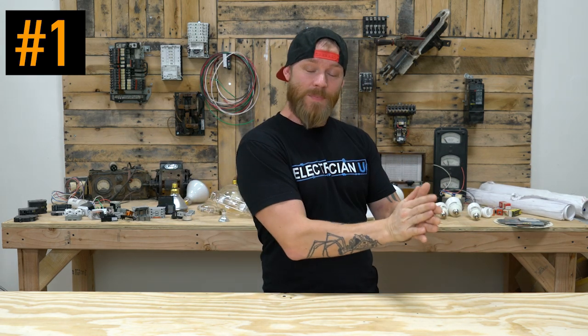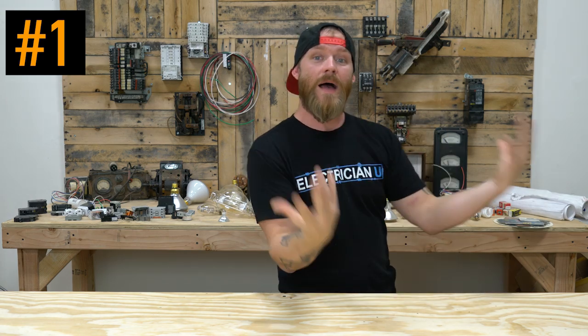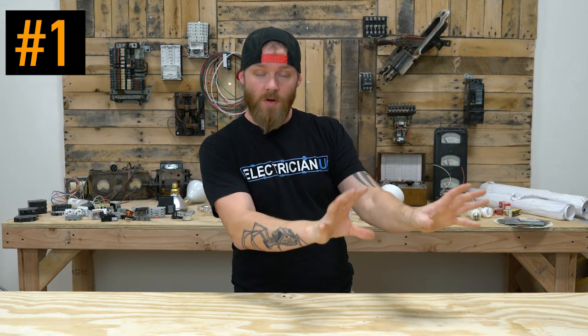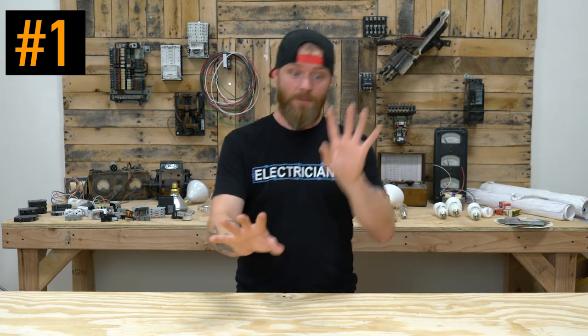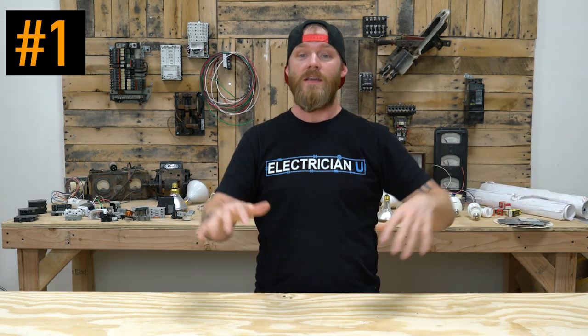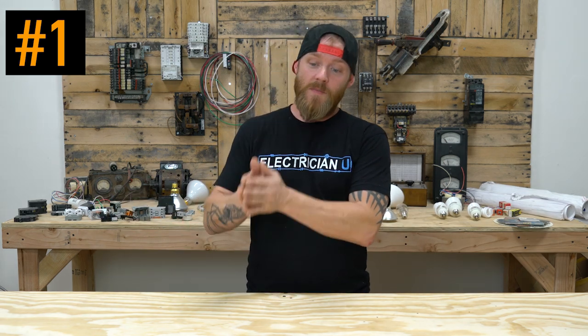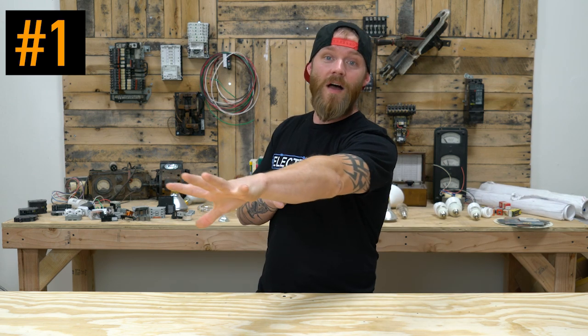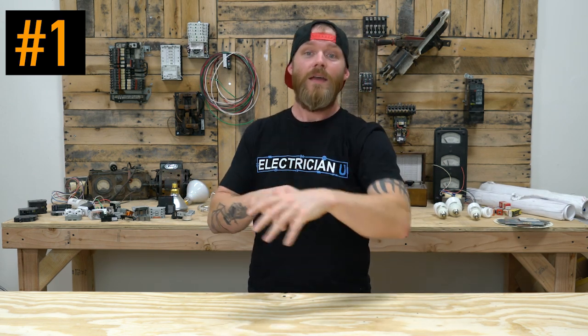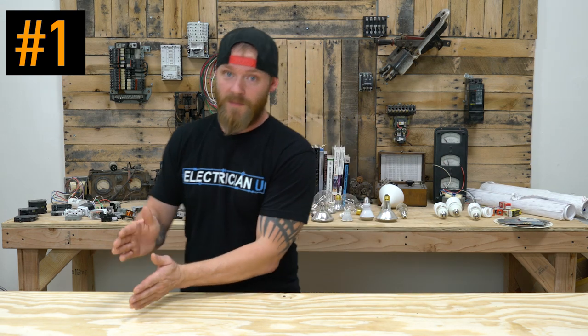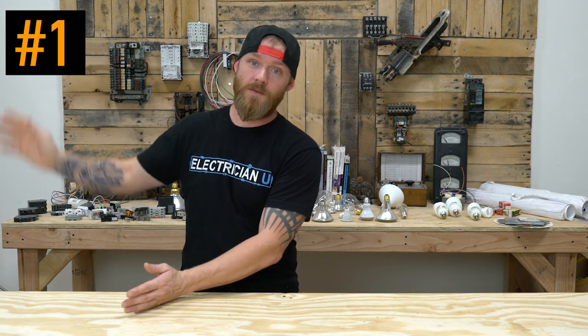So you have your service, then you've got all of your panels, you've got all this other equipment, and then at the very last panel, you've got all of these circuits that come out of it and go to devices. Those are all branch circuits. You could also have several panels that have their own branch circuits, but it's basically from the point of the last circuit breaker out to a device somewhere or an outlet. That is considered the branch circuit. Everything before that is a feeder up until you get back to the service, and then from the service on, those are service entrance conductors.